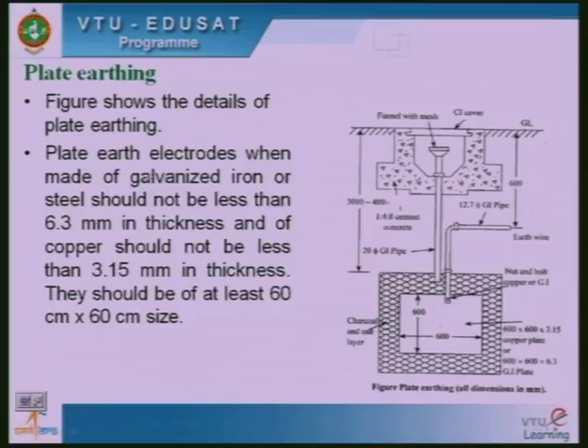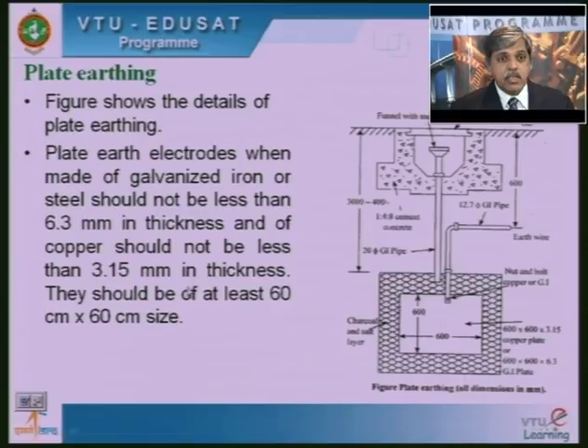Plate earth electrodes when made of galvanized iron or steel should not be less than 6.3 mm in thickness. Copper also can be used here. Instead of galvanized iron plates, I can also use copper plates. When using copper plates, the thickness will be 3.15 mm. They should be at least of size 60 centimeters by 60 centimeters. A copper plate of this size and thickness will be much costlier compared to a galvanized iron plate of the same size but larger thickness.